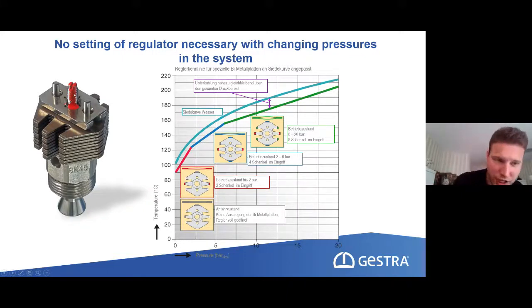But we could change something just by changing the drilling here. We can turn the stage nozzle, and by turning the stage nozzle, we can come closer to or further away from the saturated steam curve that we see here. On the first picture it was red, now it is blue, but this is the saturated steam curve, and this is the opening characteristic of the bimetallic steam trap.